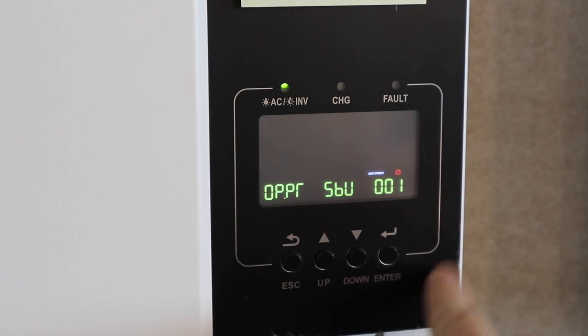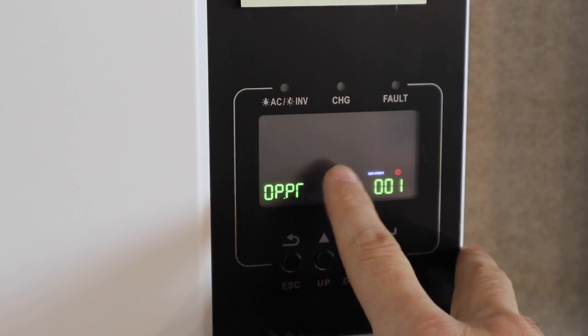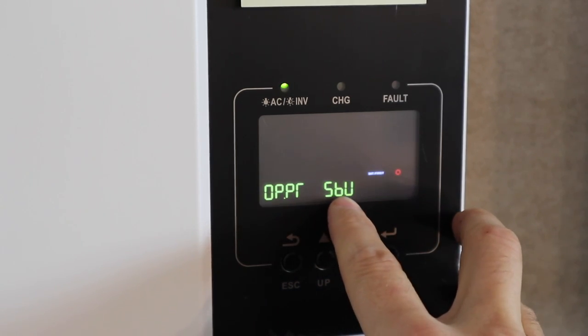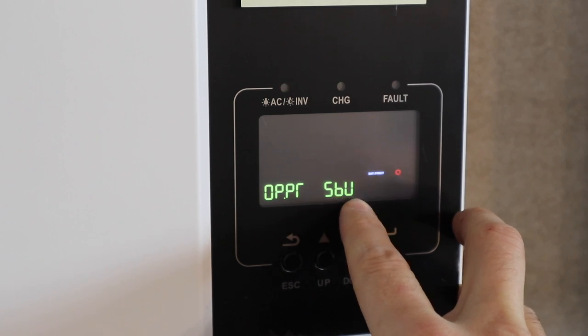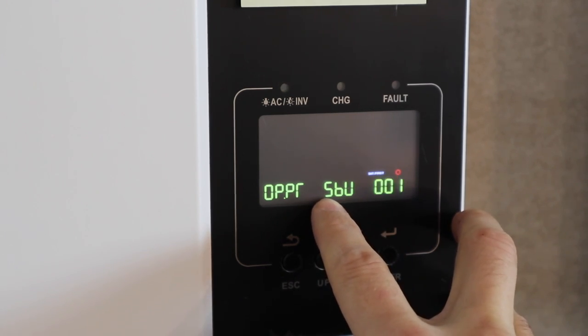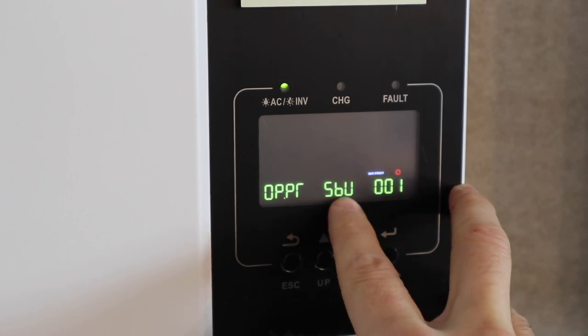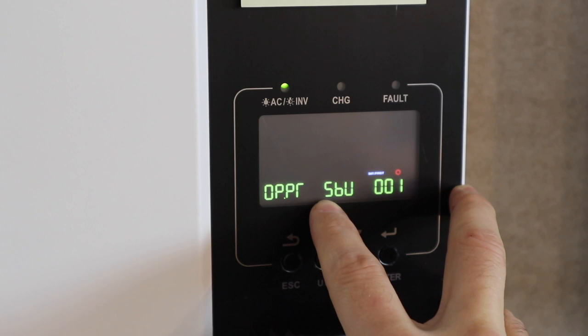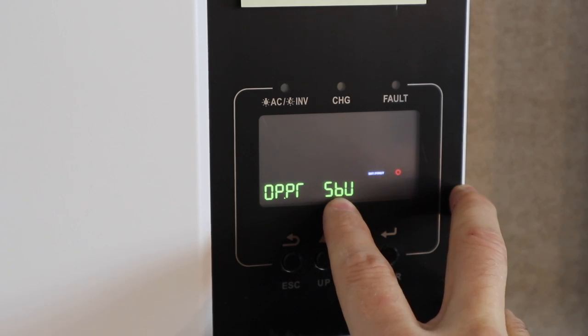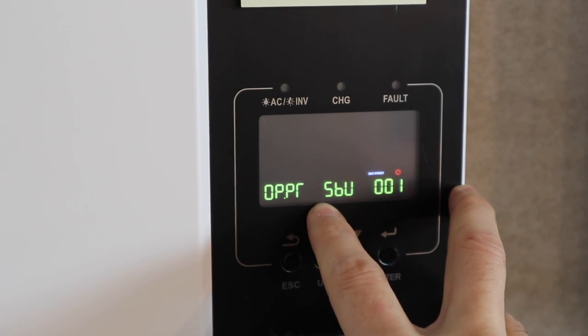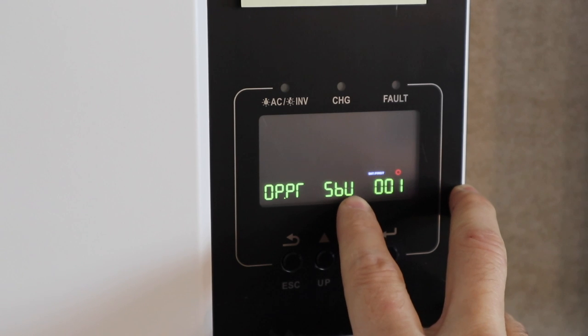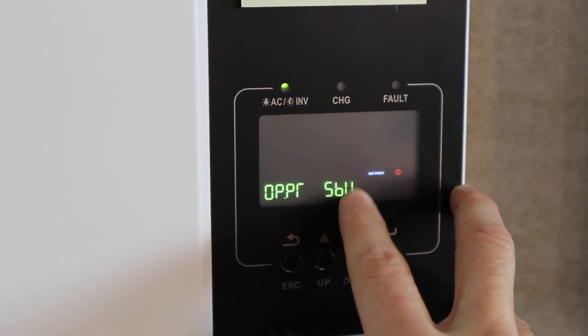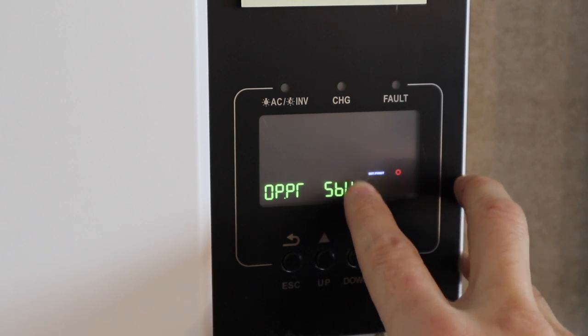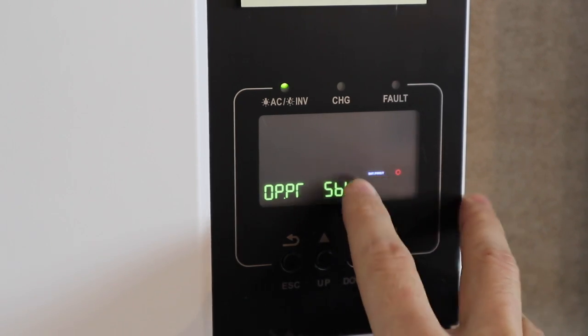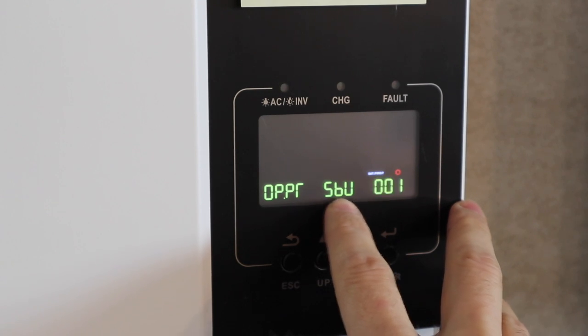So we're gonna get in here to option 1. This is our output source priority. And the SBU here stands for solar battery utility. So the loads use the power in this order. If there's sun out, it's pulling directly from the panels. If there's not a lot of sun, it pulls from the batteries. And then if the batteries are low and there's no sun, it'll pull from the utility. But for us, we don't have AC in. It's not hooked up because we're completely off grid. So that U really doesn't exist for us. So this you'll want to change because the default is set at utility.